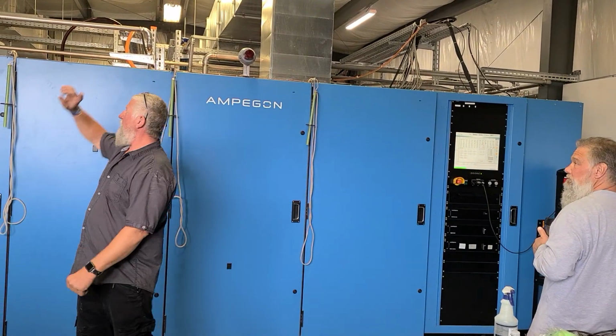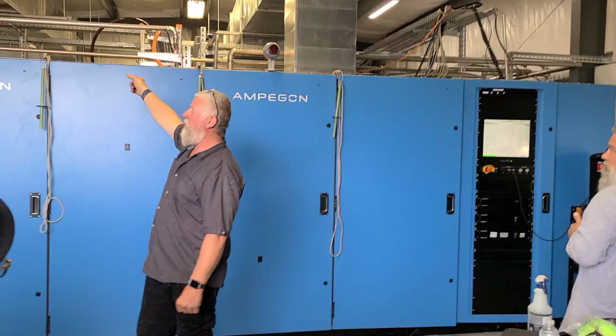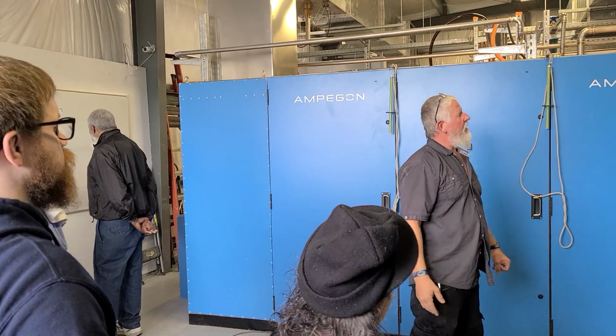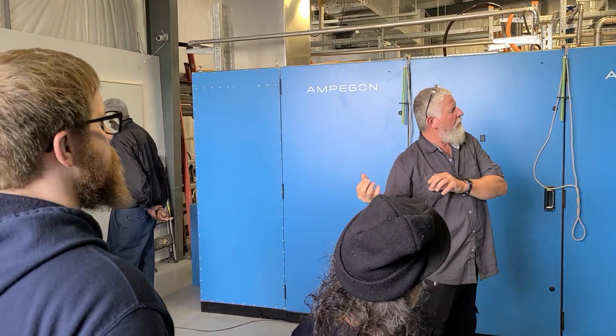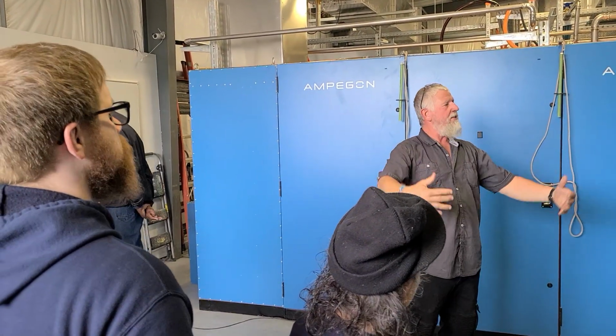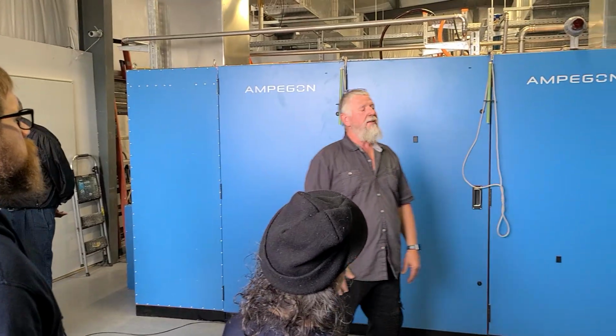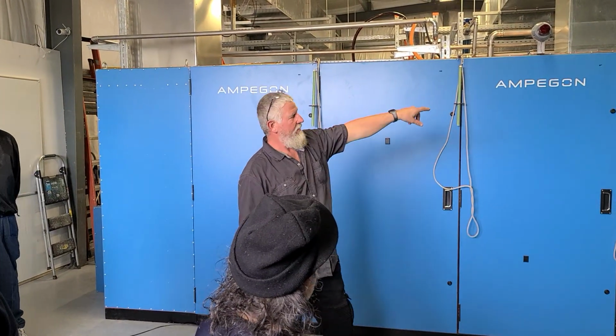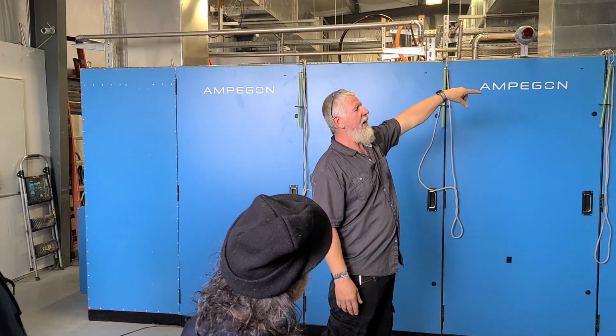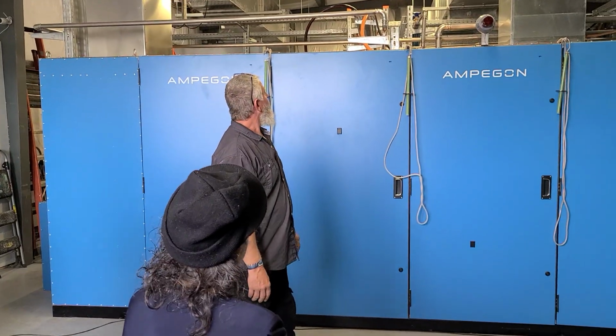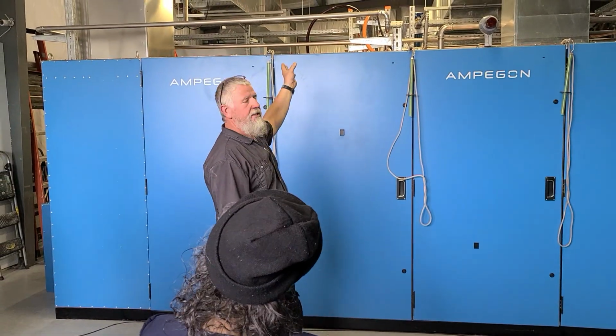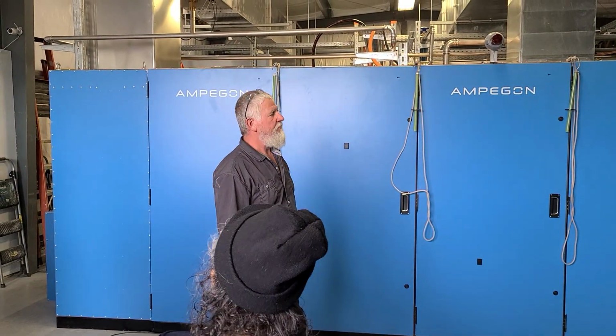Then we have the test load in the back corner. That's the big one, because you're taking 300,000 watts of power and dumping it into a little space, it's got to get rid of all that heat. So that's the bigger system along the back wall, also inside-outside, closed loop with heat exchangers.